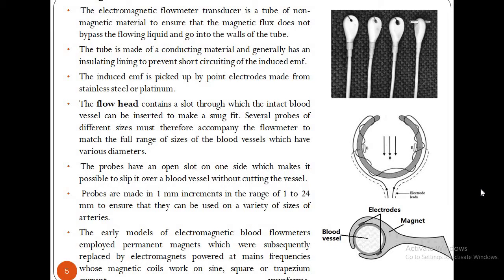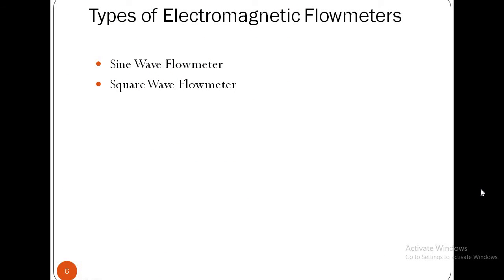The early models of electromagnetic flow meters employed permanent magnets, which were subsequently replaced by electromagnets powered at mains frequencies, whose magnetic coils work on sine, square or trapezium current waveforms. So depending upon the shape of the energizing current waveform for the electromagnet, there are two types of electromagnetic flow meters. They are the sine wave flow meter and square wave flow meter.